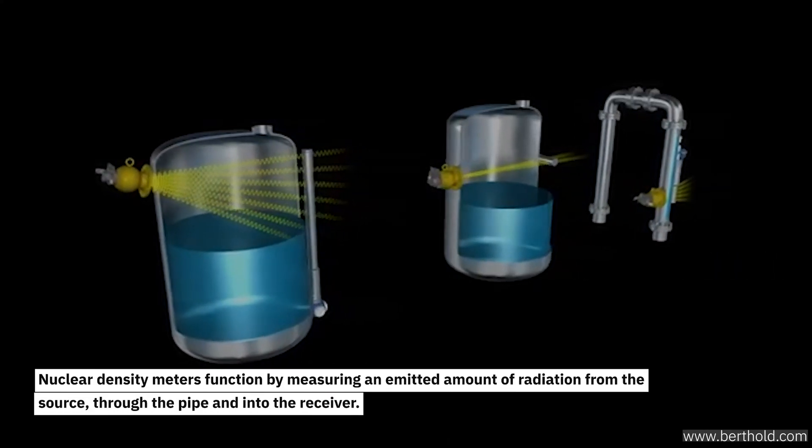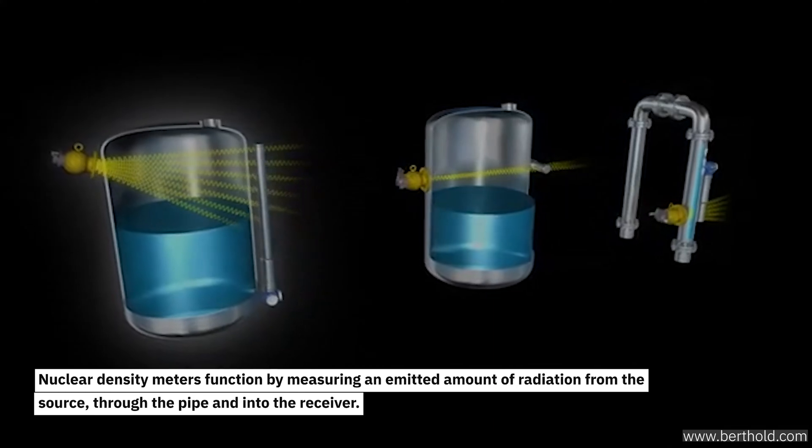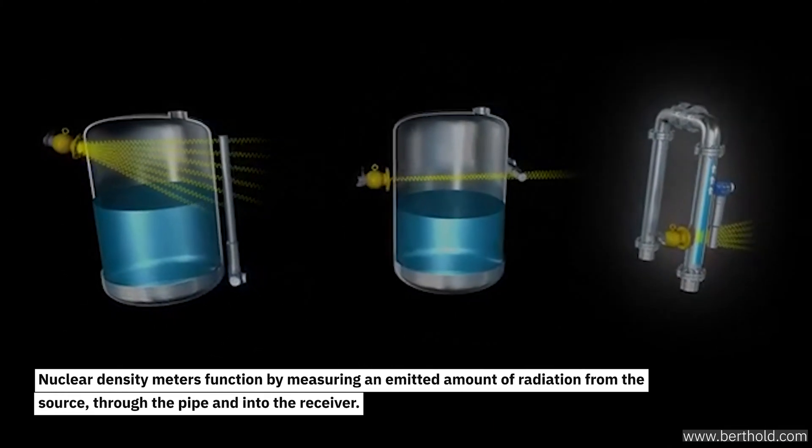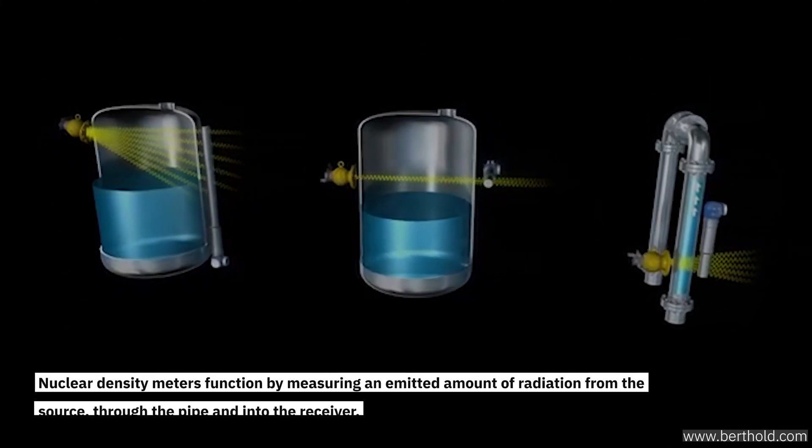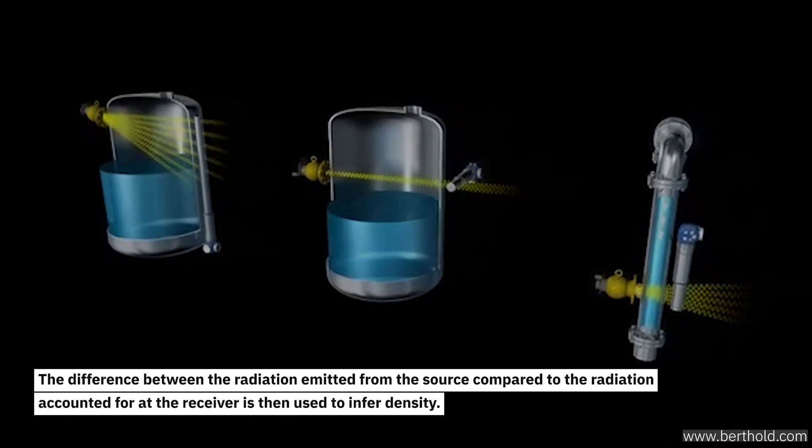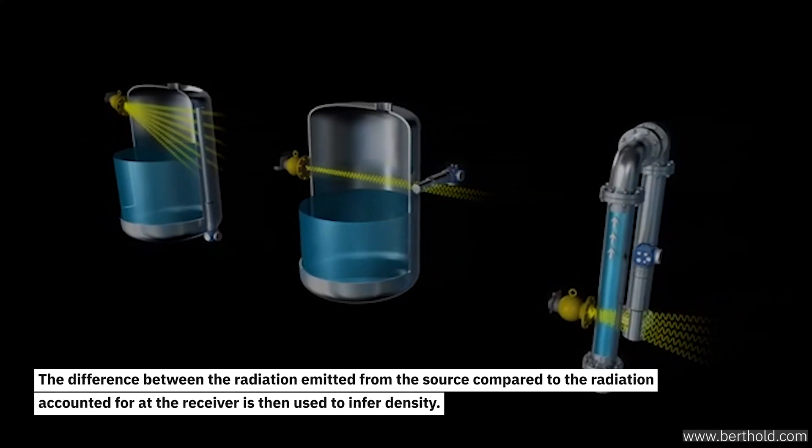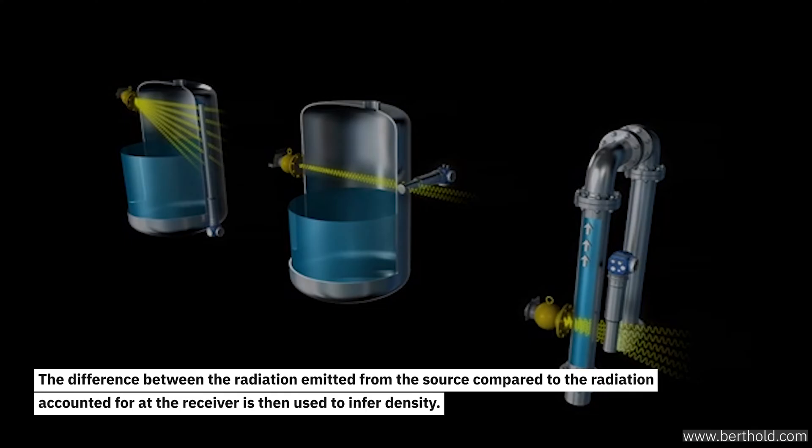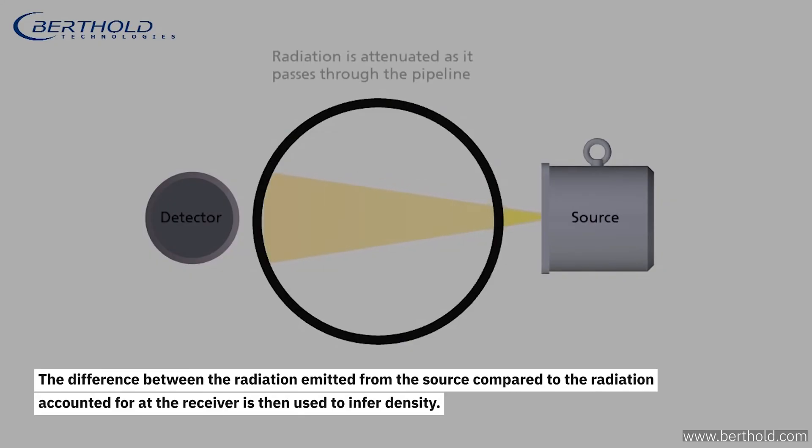Nuclear density meters function by measuring an emitted amount of radiation from the source, through the pipe, and into the receiver. The difference between the radiation emitted from the source compared to the radiation accounted for at the receiver is then used to infer density.